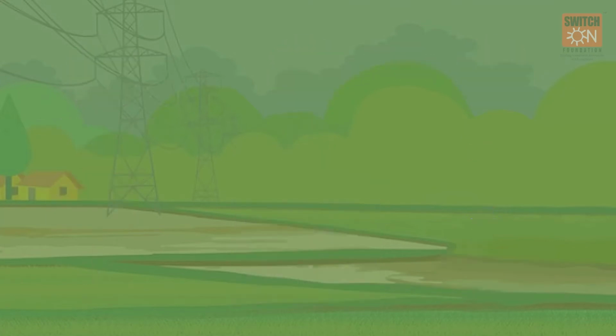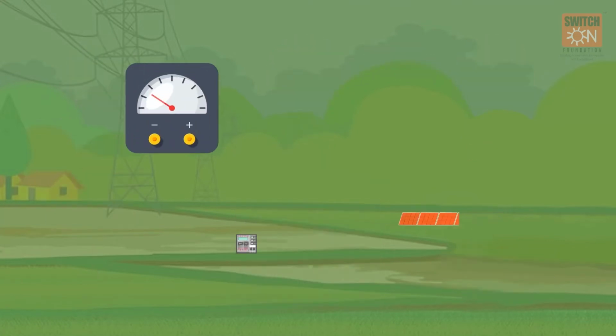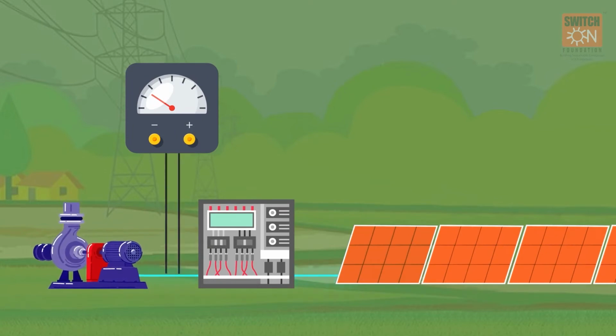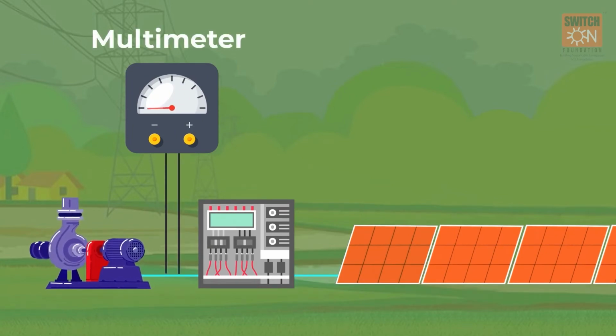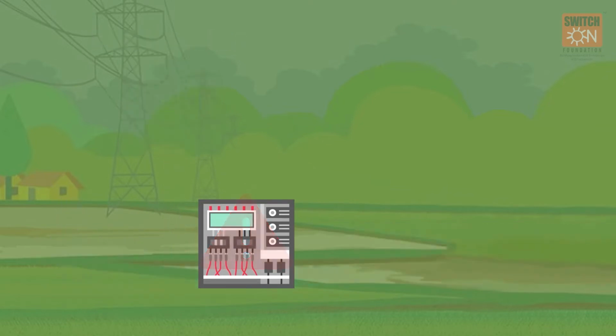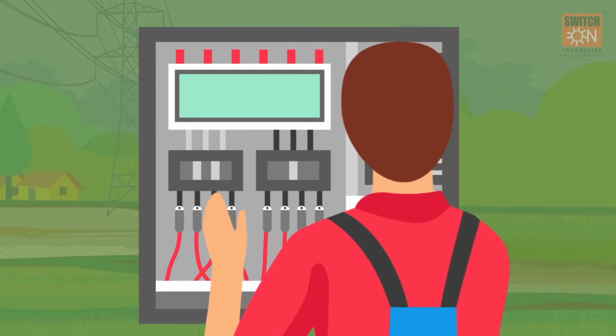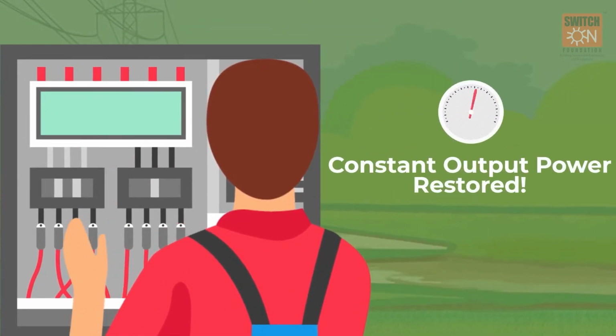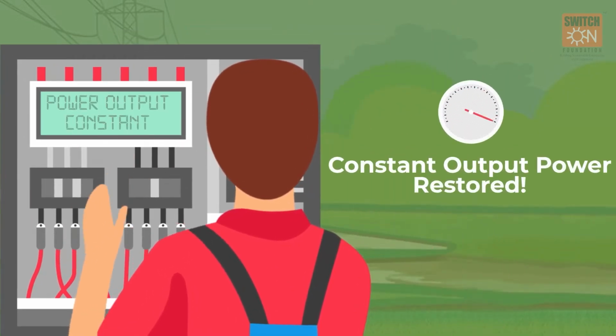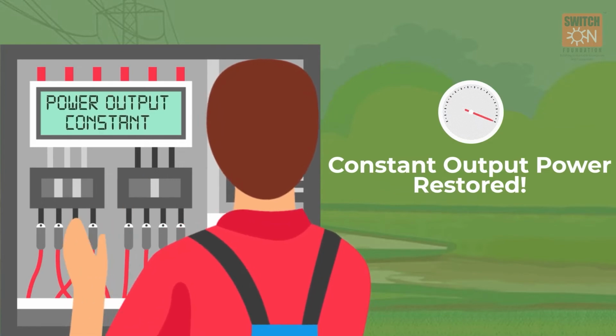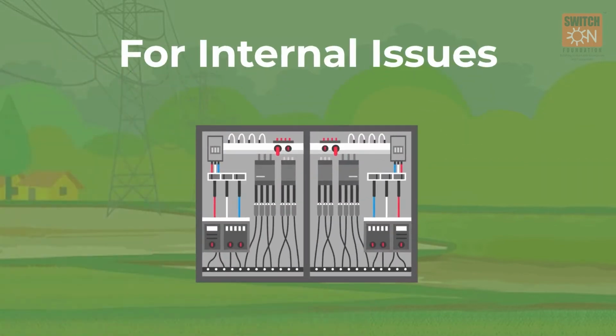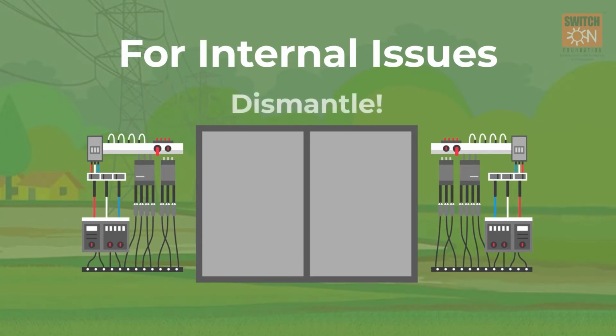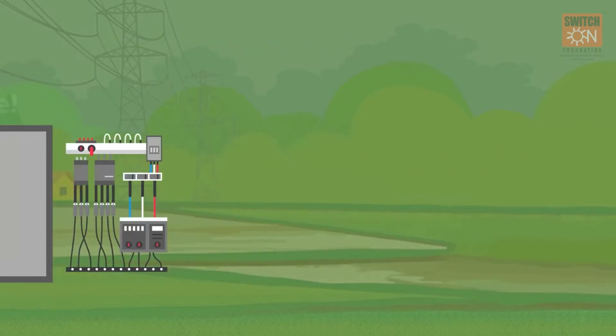In the third step, check for the continuous power output from the solar array by using a multimeter. If there is a big fluctuation in power output, it must be the issue of the controller. The servicing technician can modify the controller setting to ensure constant power output is restored. Otherwise, if there is an internal issue of the pump controller, then it has to be dismantled and taken to a servicing center for further diagnosis.